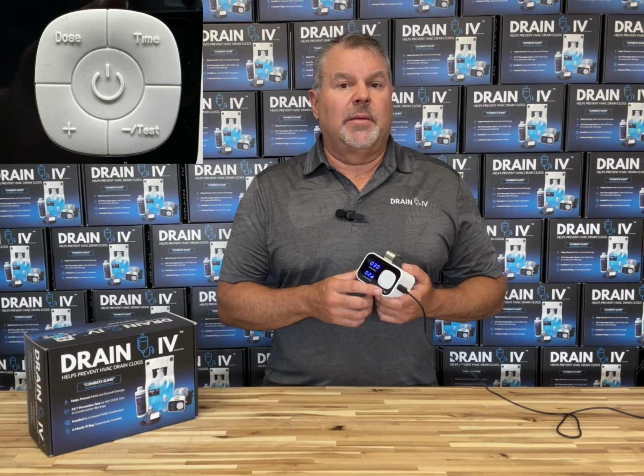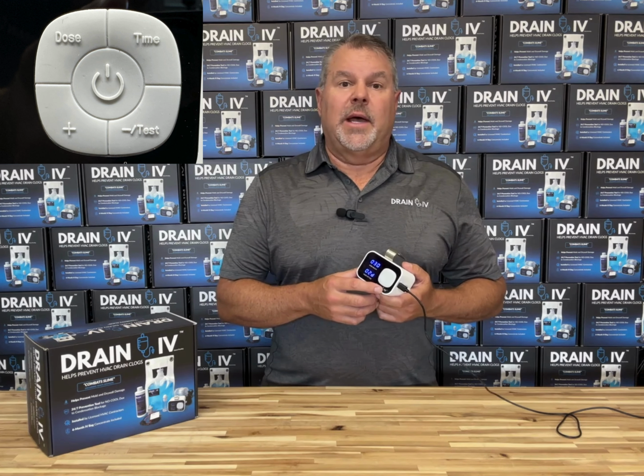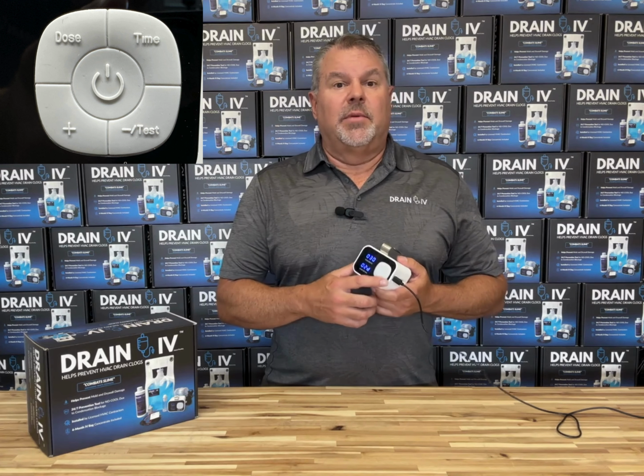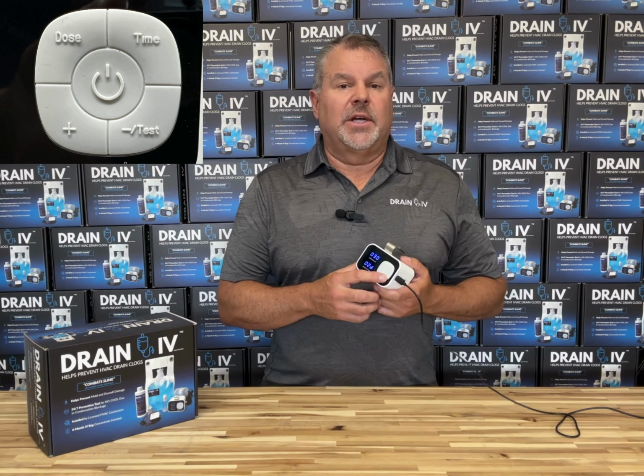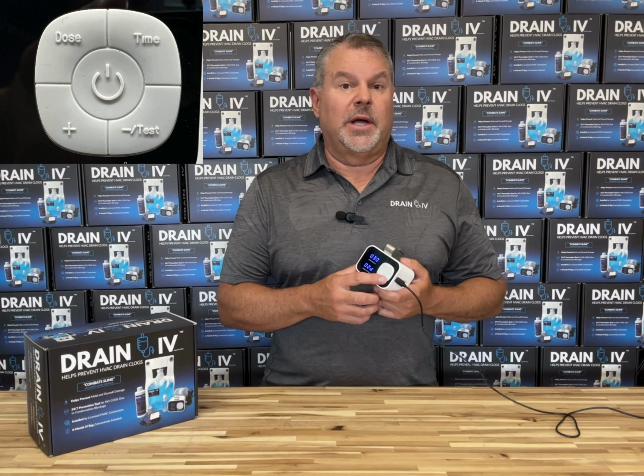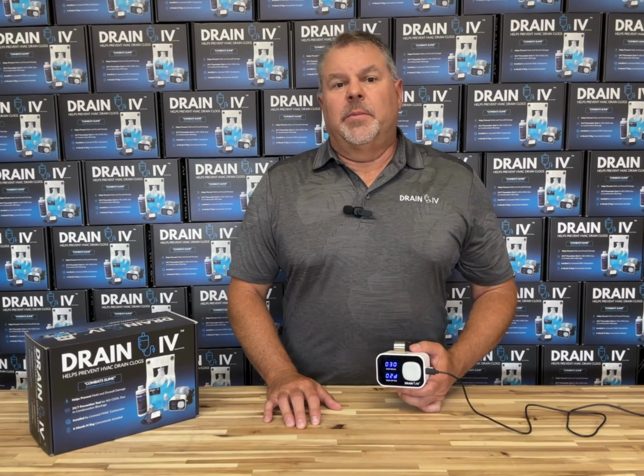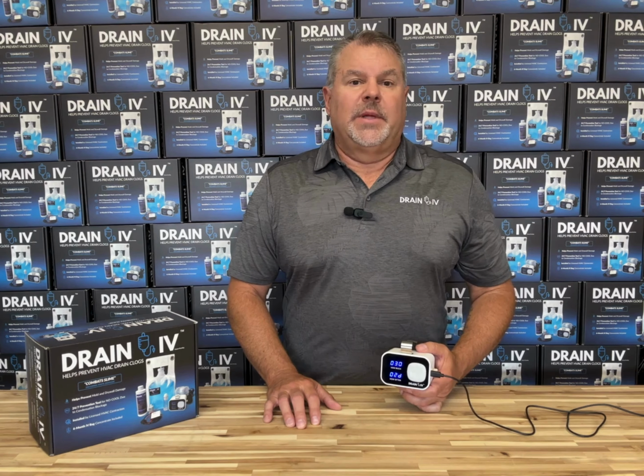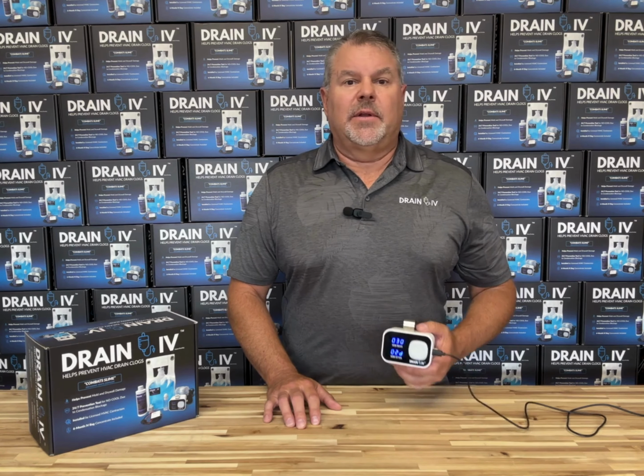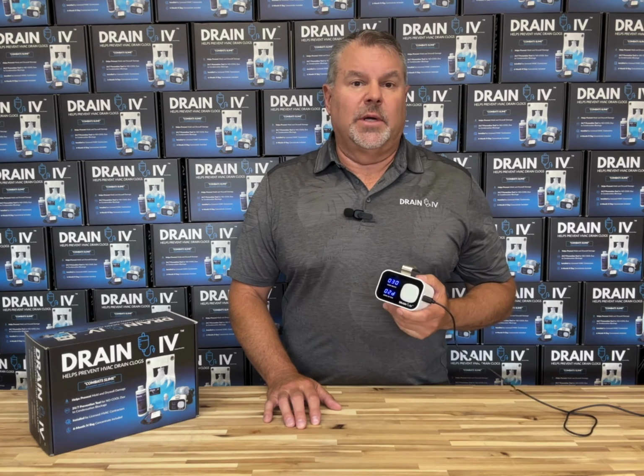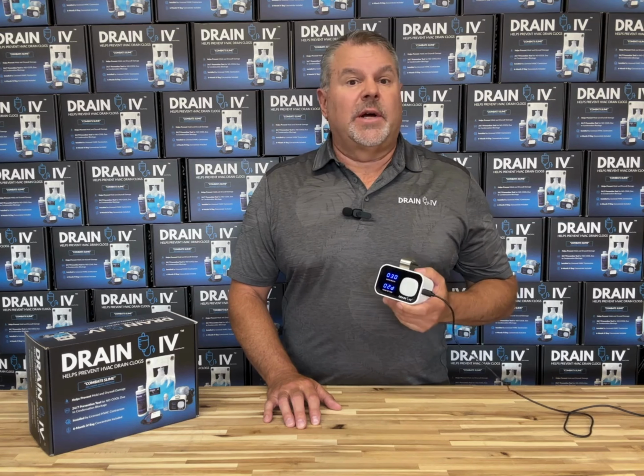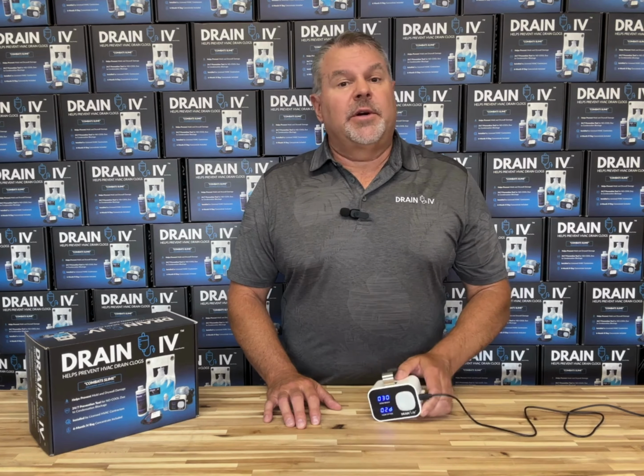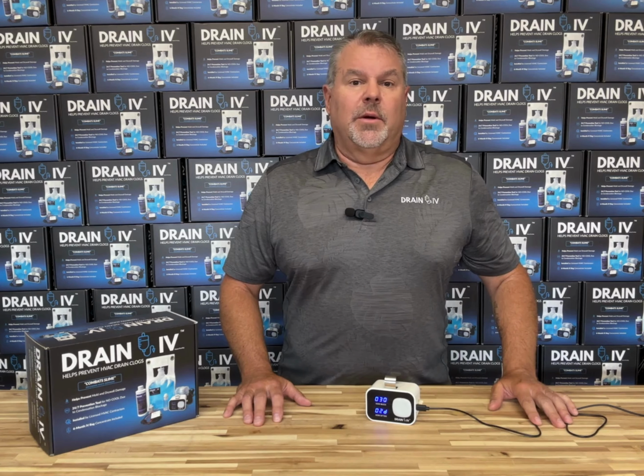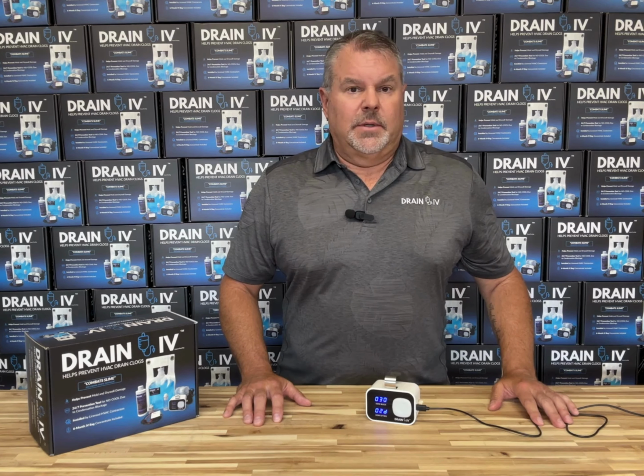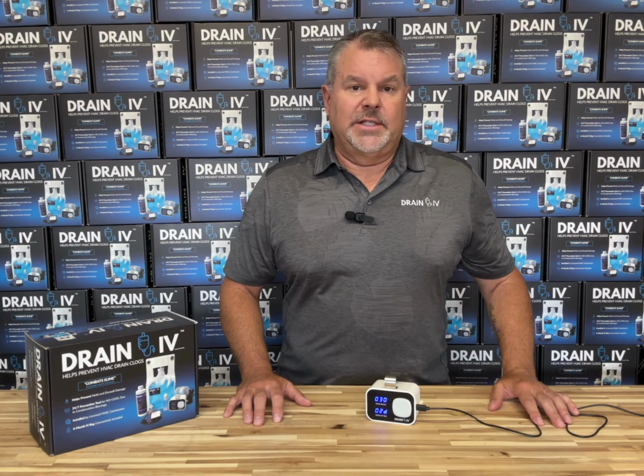Test is also used to prime the tubing on install or when the IV bag is refilled. On install, press the test button as many times as it takes to flush the air out of the tubing and verify that the fluid is being delivered to the drip tray or injection port. Okay, now that the pump is programmed, you're ready to go. The pump's timer will start immediately after the last dose or time setting was confirmed or the pump was powered on, whichever action was last. When the timer expires, the pump will run the programmed dose. Then the timer restarts. Note that when you run tests, the timer is not reset.